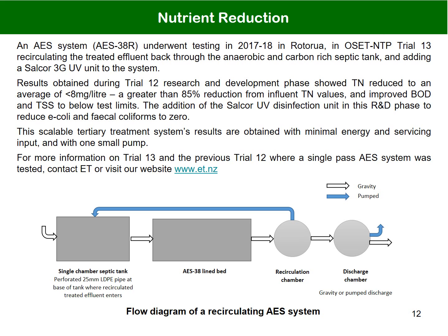to below test levels. The addition of the Salcor unit in the R&D phase showed E. coli and fecal coliforms reduced to 0. This scalable tertiary treatment system's results are obtained with minimal energy and servicing input and one small pump. For more information on Trial 13 and the previous Trial 12, where a single-pass AES system was tested, you can contact ET or visit our website et.nz.